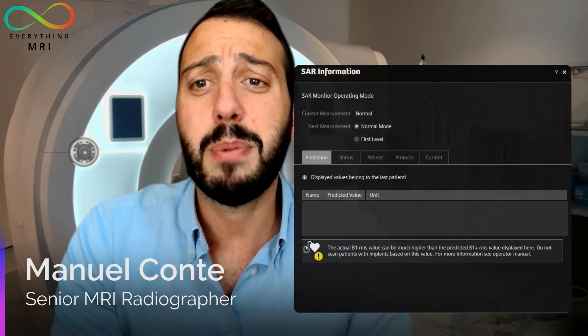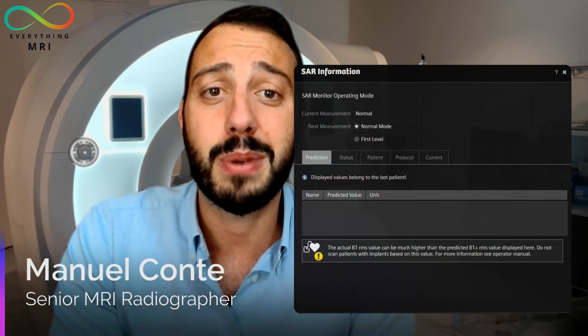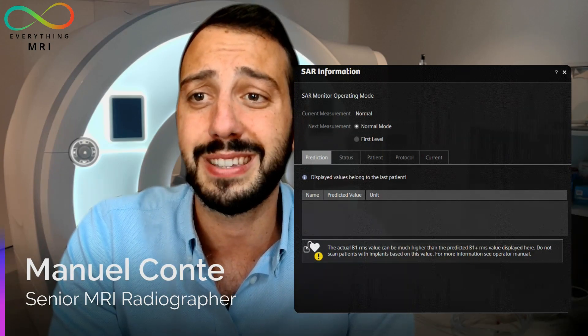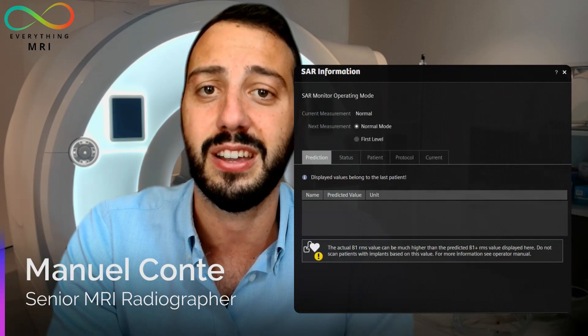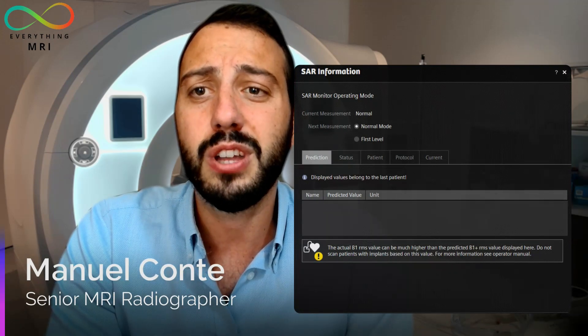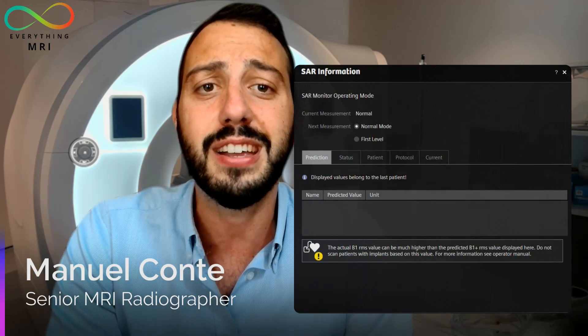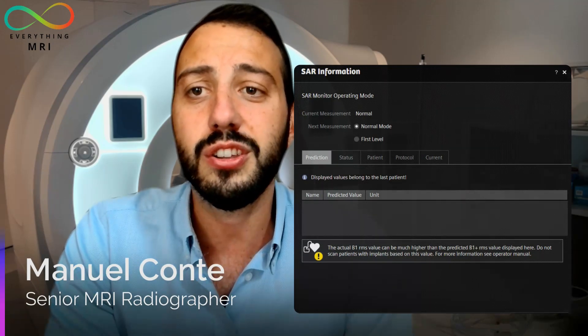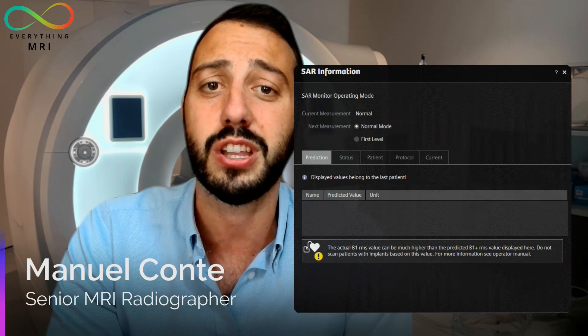Nevertheless, a number of MRI safety considerations should be made. Most implants nowadays are paramagnetic, so generally safe in MRI. However, some older implants contain ferromagnetic components that might pose risks at high magnetic field strength, especially regarding heating. This means that when scanning at 3T we might have to deal with significant SAR conflicts and several considerations regarding the SAR operating mode to be used — considerations that are less likely to be a concern when scanning at 1.5 Tesla.